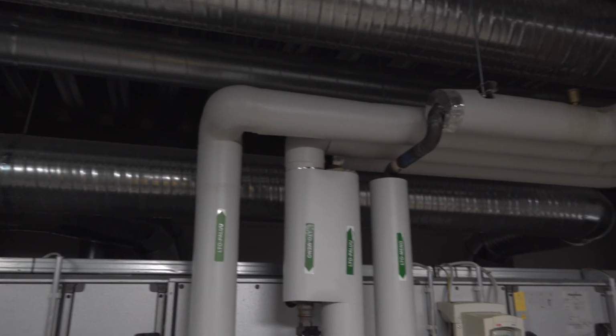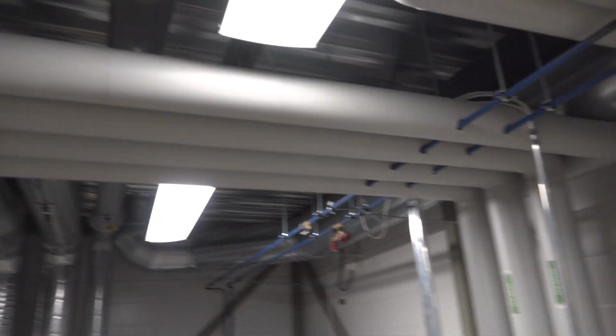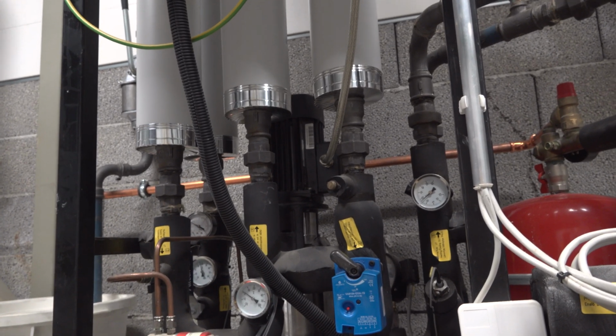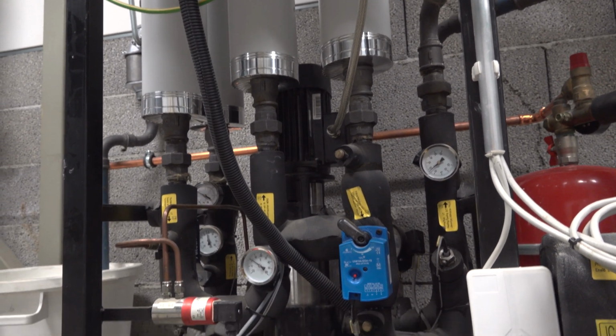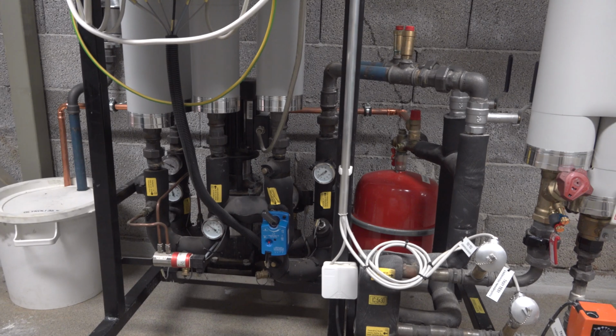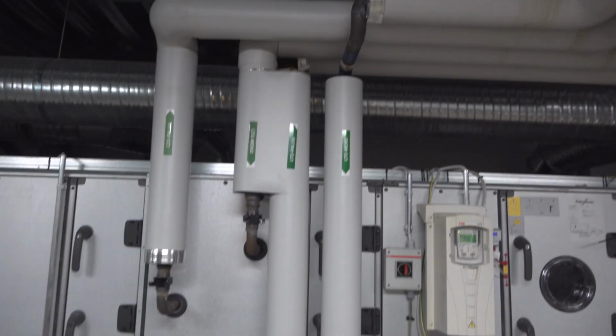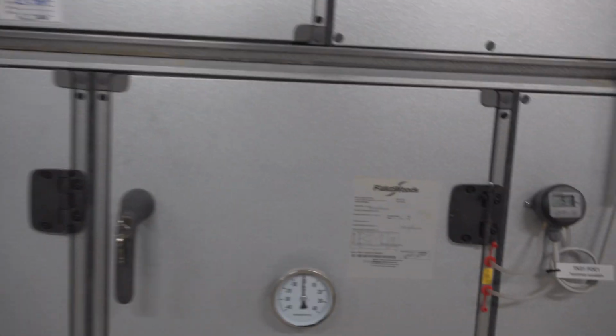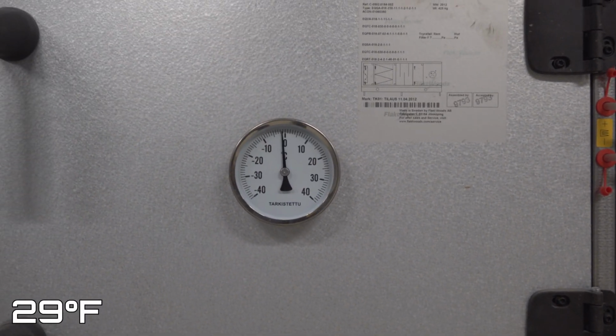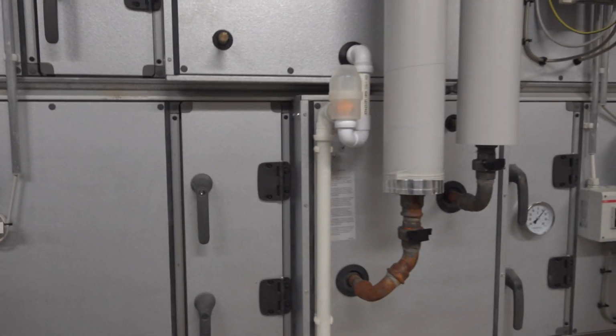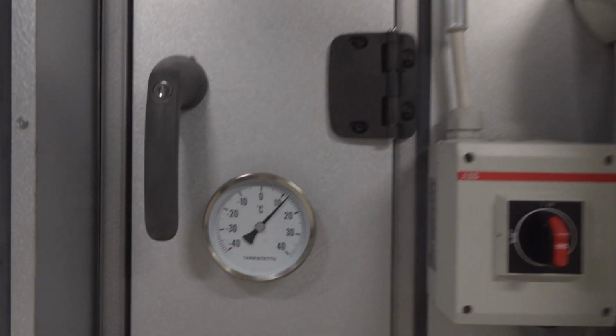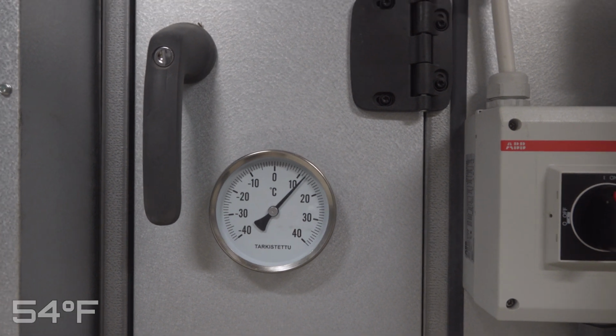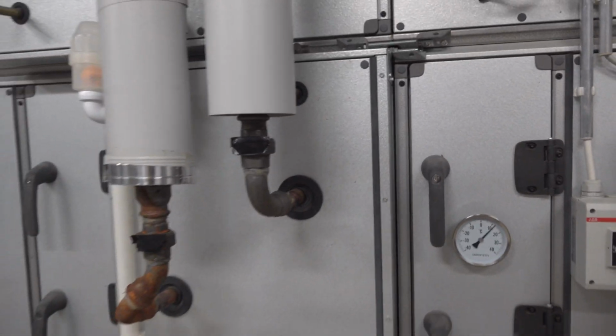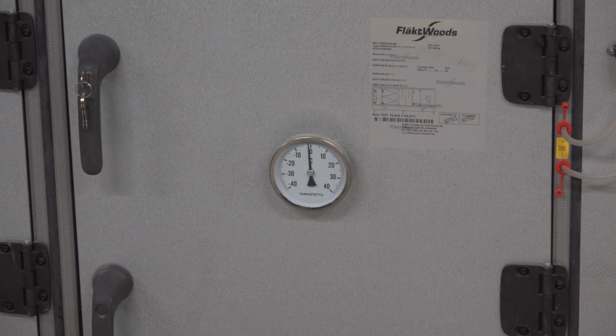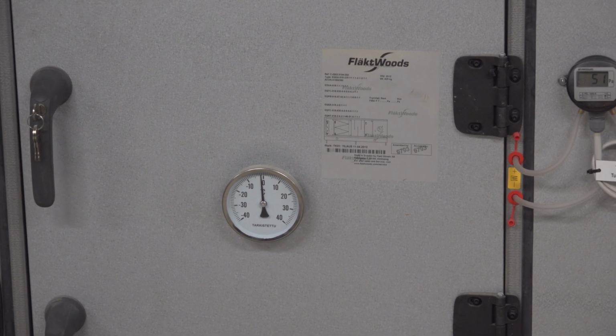These tubes here go to the heat exchanger circuit, which is on the other side of the room. There is a small motor here which circulates the water ethylene glycol mixture back through the other tubes to the lower portion of the heat exchanger. If we check the input temperature, it's a bit under freezing point. And after the heat exchanger, it's about 13 degrees. So we add about 15 degrees of temperature in the heat exchanger here. The mechanical heat recovery is enough to heat up all the input air that comes to the house.